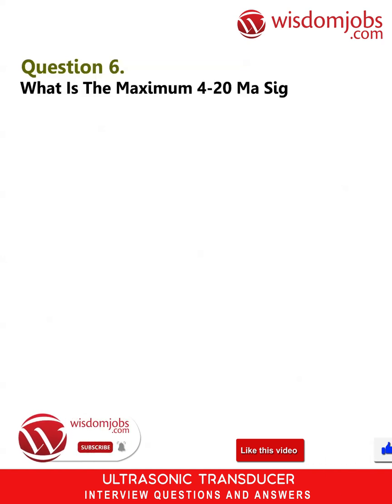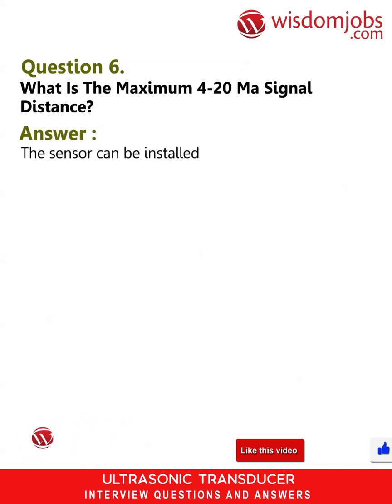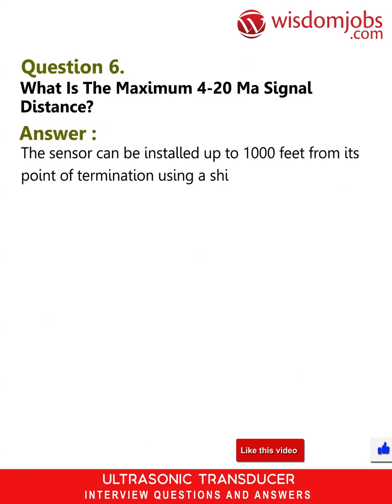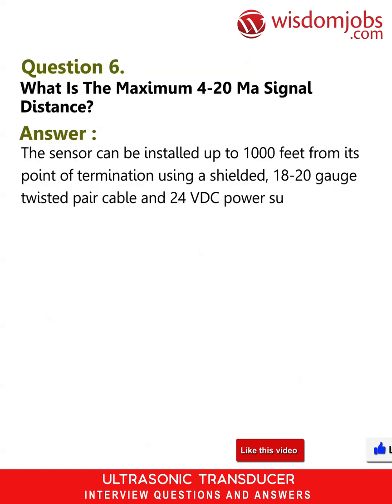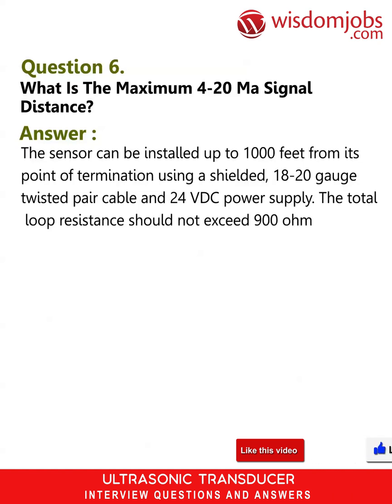Question 6. What is the maximum 4 to 20 mA signal distance? Answer. The sensor can be installed up to 1000 feet from its point of termination using a shielded 18 to 20 gauge twisted pair cable and 24 VDC power supply. The total loop resistance should not exceed 900 ohms. Changes from vendor to vendor.